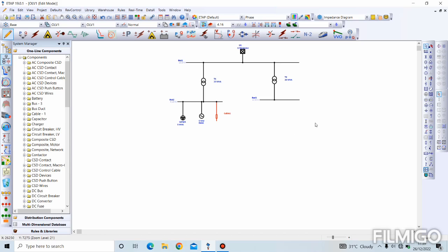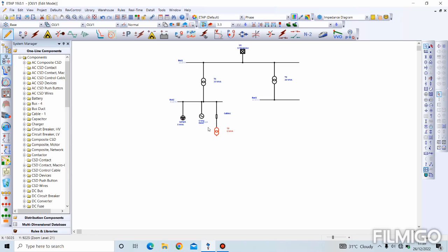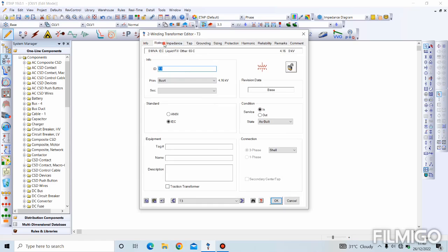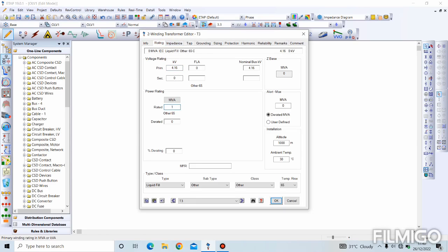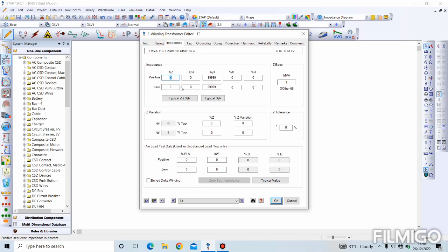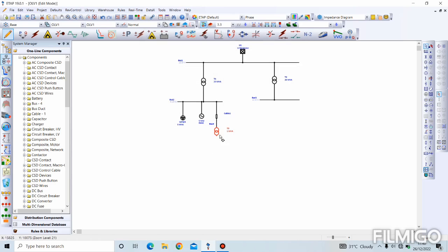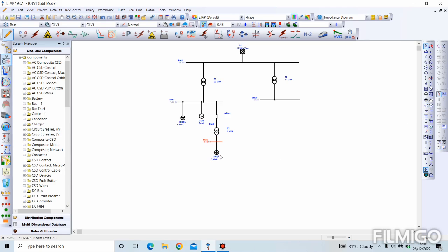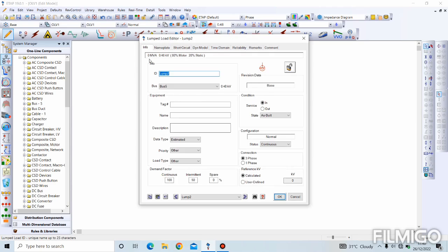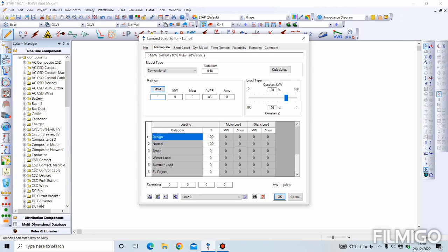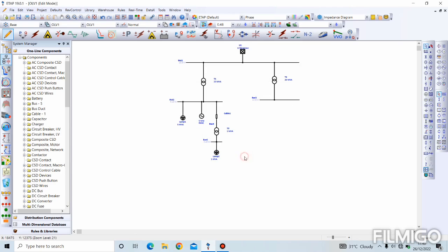Then, we connect a transformer. I will be connecting a transformer to this cable directly. However, we can see that bus 4 was created. This is as a result of when two impedance components are being connected together. ETAP automatically inserts a node bus. That is what formed this bus 4 here. Transformer ratings. Let's say 1 MVA. Voltage 0.48 KV. To a bus bar. And then, to a lump load.